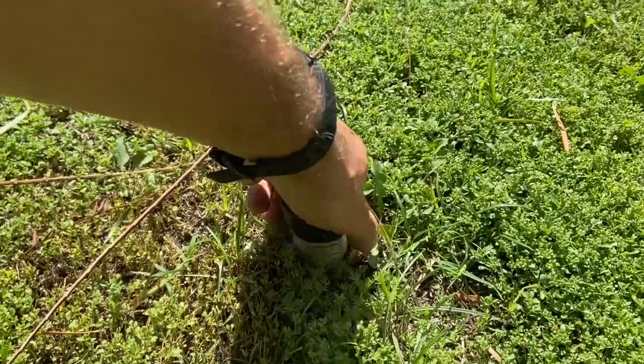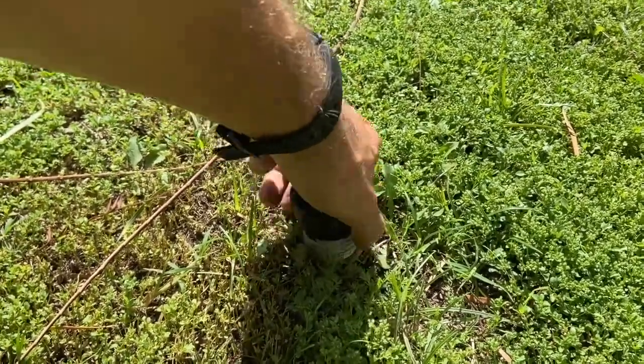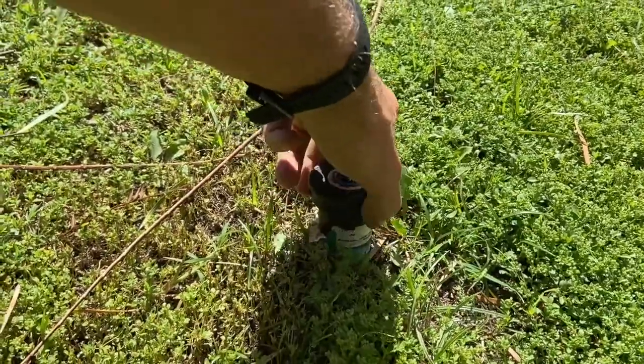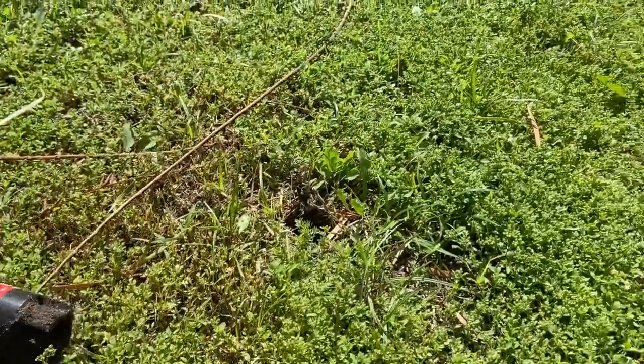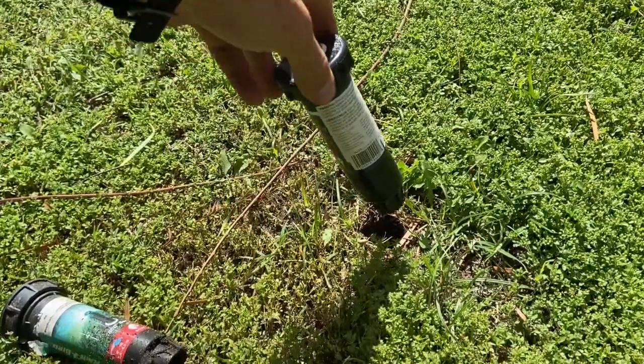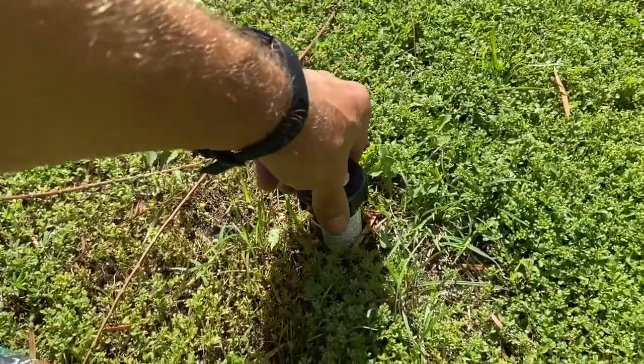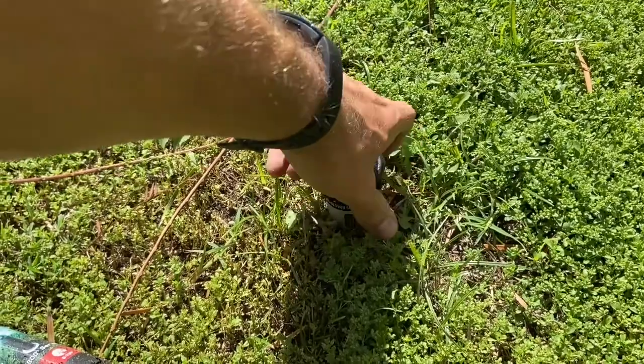If it's just the sprinkler head that you're replacing and there's nothing else that's wrong with your system, it's a really straightforward fix. What you're going to want to do is grab the sprinkler head at the body of the sprinkler, twisting until it comes off of that riser. And then if there's nothing else wrong with the sprinkler system, if you didn't have any leaks outside of the sprinkler head, it's as simple as putting a new sprinkler head back in directly where that other sprinkler head existed.